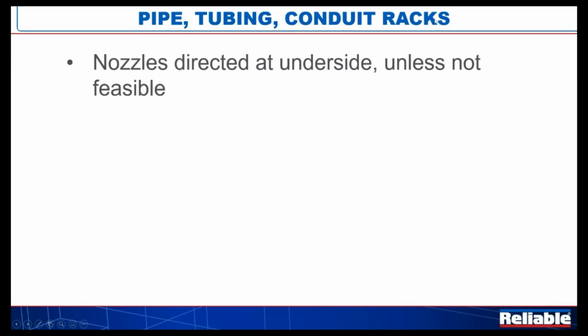Piping, tubing, and conduit racks. Interestingly enough here, we want the nozzles directed upward at the underside, unless it's not feasible. But where feasible, the nozzle should be directed up, pointing to the underside. There was really no language, and I didn't have the handbook to understand why that is. I presume it's got something to do with something that's happened in the past. But in any regard, you're allowed to put it at the top if you have to.